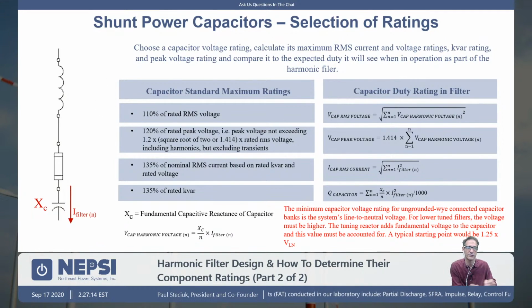capacitor. Now, capacitors by standard can handle 110% voltage. They can handle 110% voltage, but when you do your design for your filter, you want to basically design the filter so that it's at 1 per unit, no greater than 1 per unit, that RMS value. That 10% additional voltage rating is really for your system voltage regulation. The utility in your supply typically can be plus minus 10% voltage. So you need to hold on to that additional 10% voltage that the capacitors allow for the fundamental voltage of the system. The other test that you're going to be doing is 120% rated peak voltage.